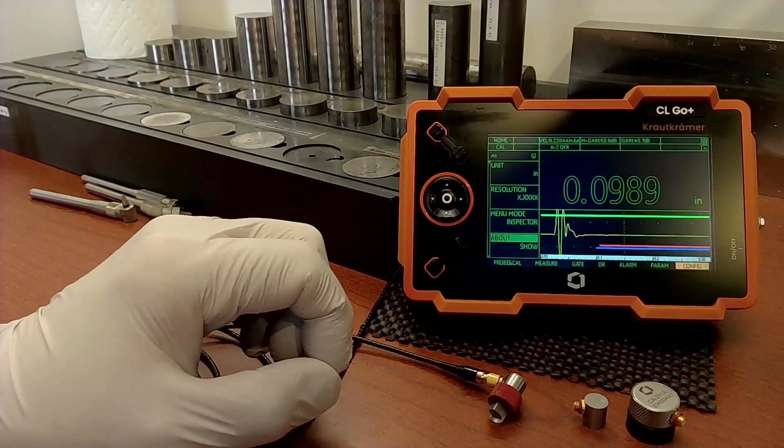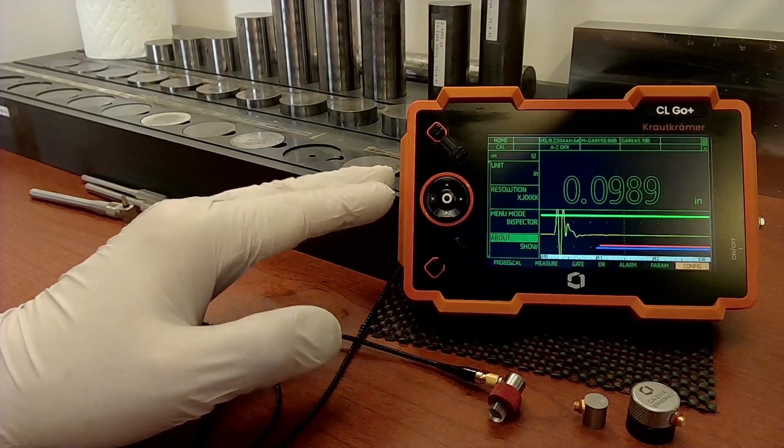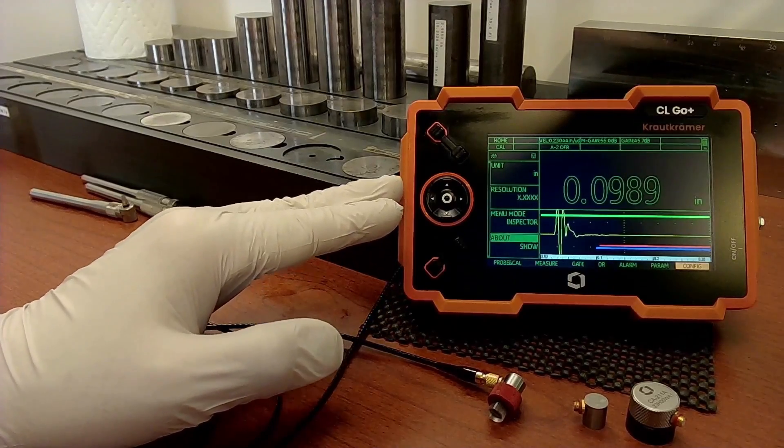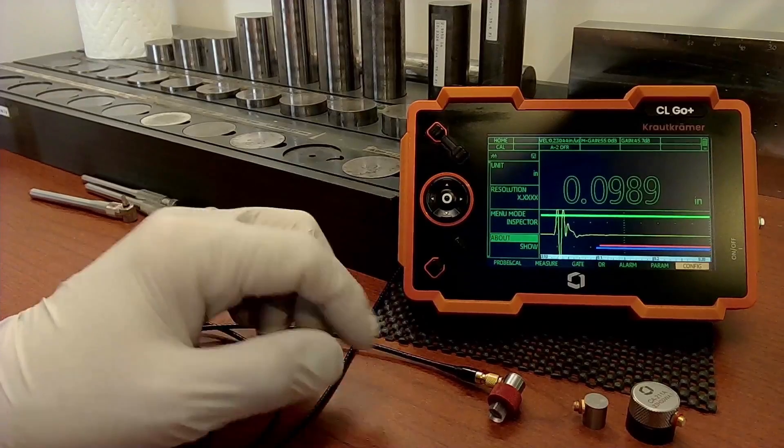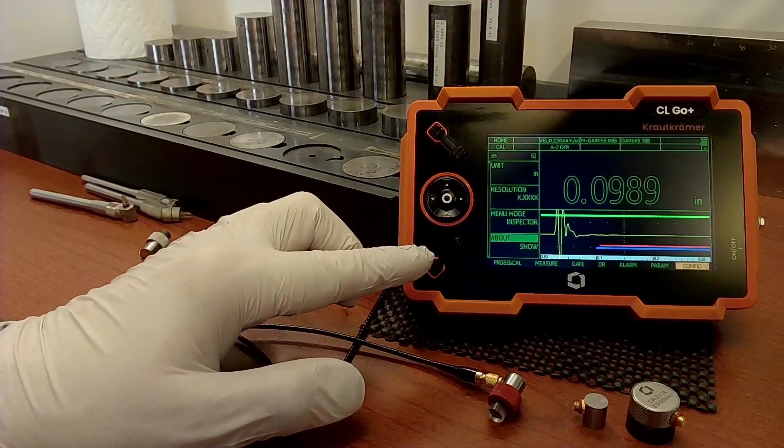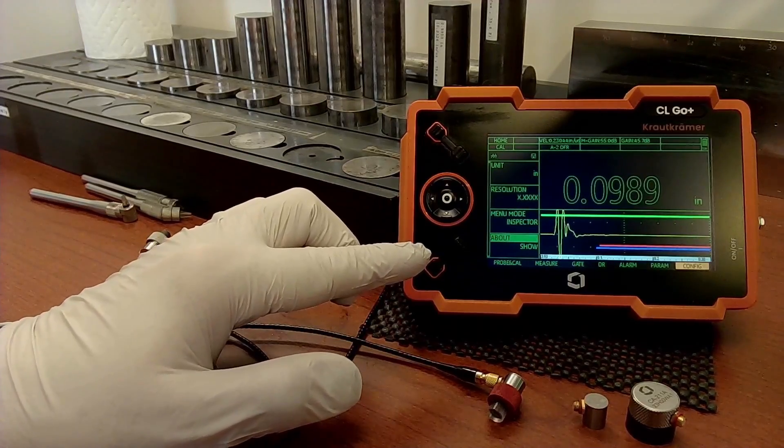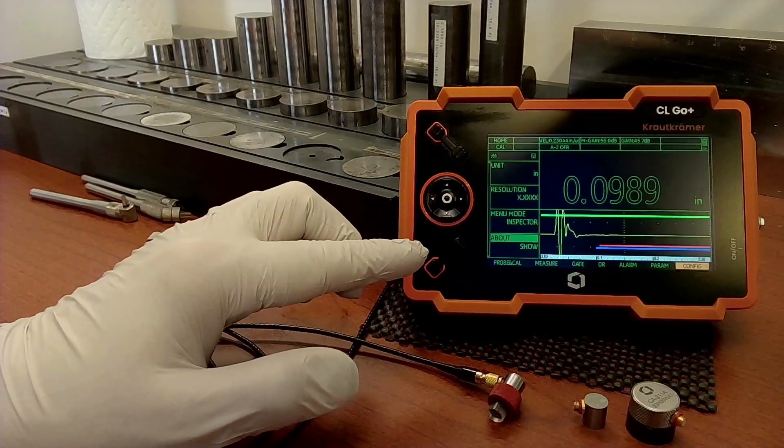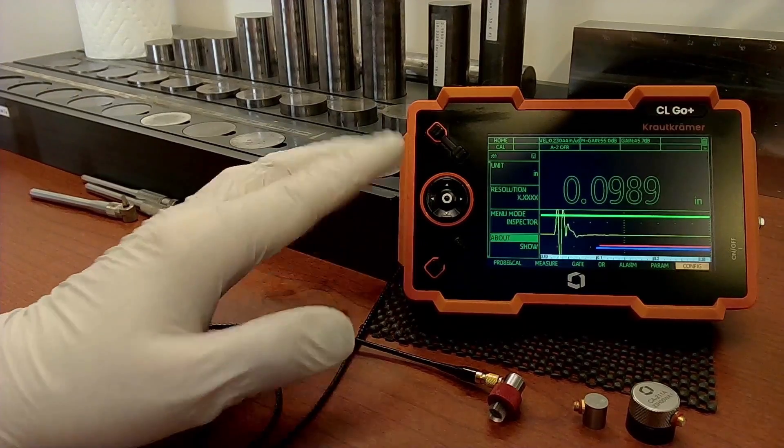To achieve those levels of precision, there are additional digital signal processing techniques that we implement in the CL Go+ platform. And we also use a different series of probes than we would normally use in a corrosion thickness gauge like the DMS-GO.